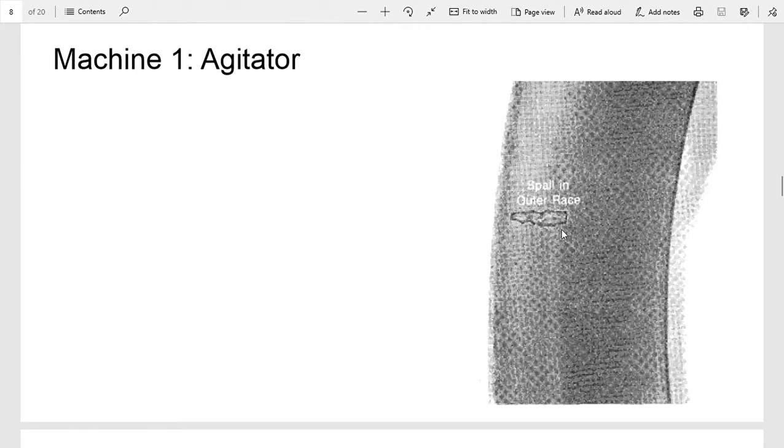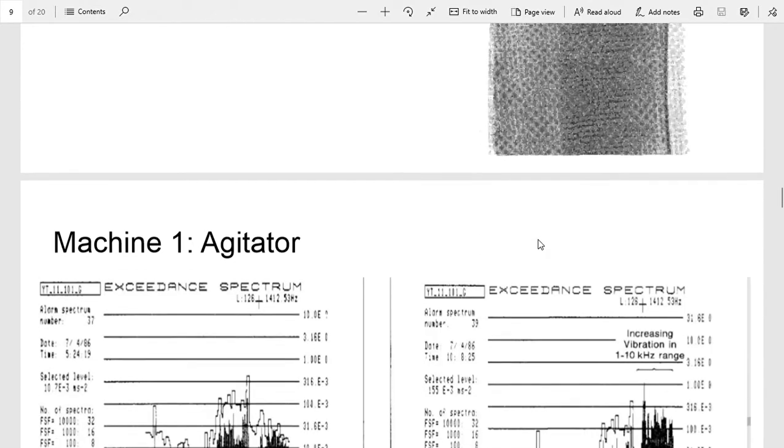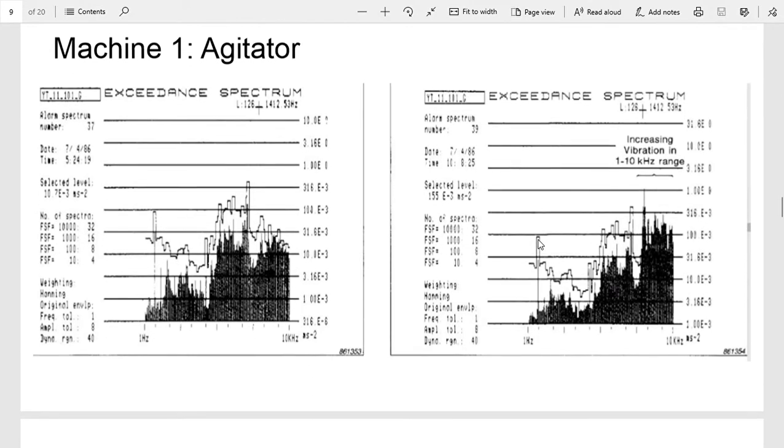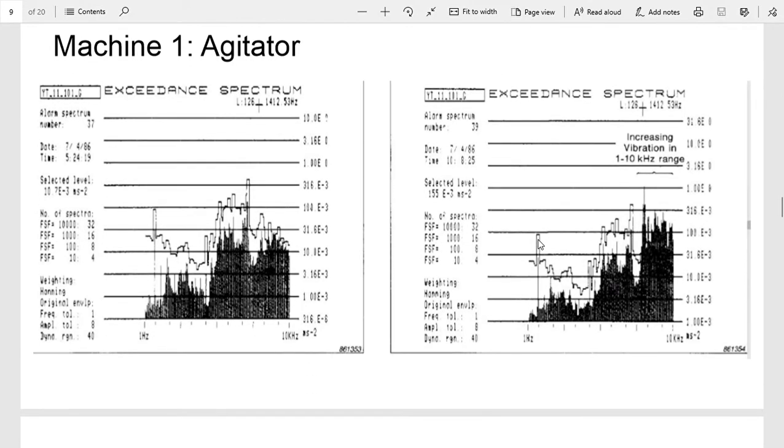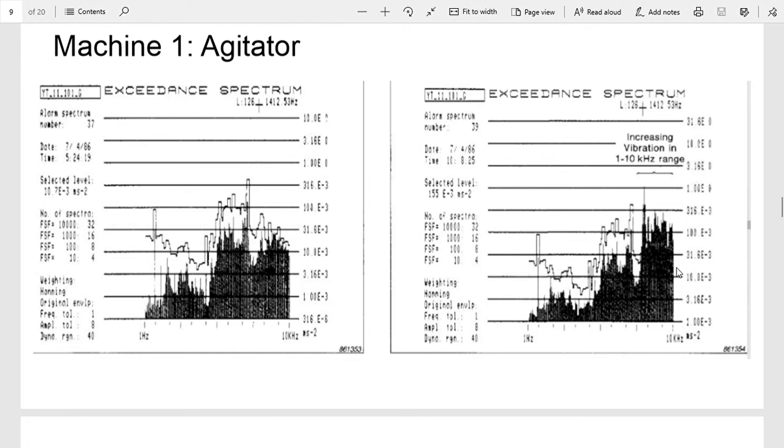But this was a pretty minor fault. They figured they could have run that bearing for quite a while, but still a fault nonetheless. A little while later, during a scheduled PM, they found that there's a sudden increase in vibration. You can see from here to here there's a definite increase in these higher frequency data ranges.